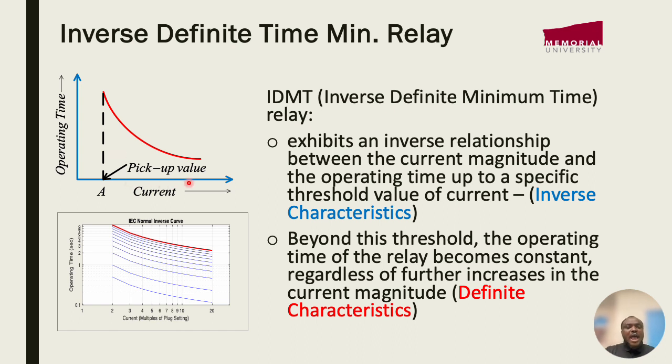Whereas when we have a higher current, this relay takes a relatively shorter time to react. That is the inverse characteristic of this IDMT relay.